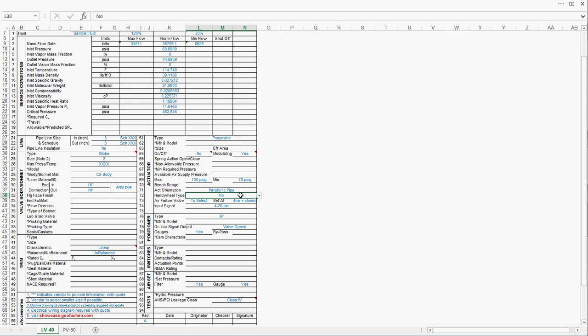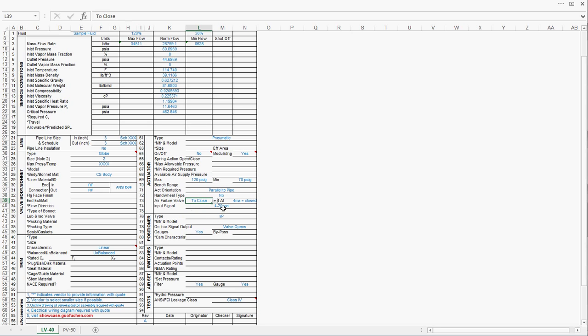Hand wheel, most of the time no. In case of the instrument air fail, that valve is going to open or close. In this case, we have a fail close valve, so we choose to close. And this actuator in general accepts 4 to 20 mA signal, with 4 mA equal to closed.